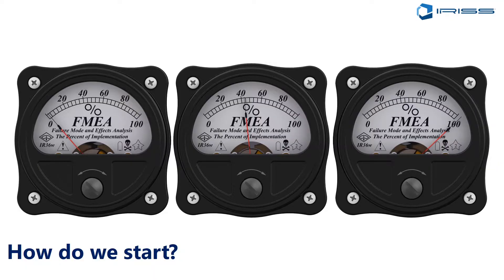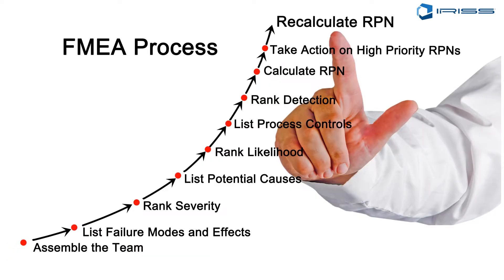So much has been written on the why and the what of electrical maintenance programs, but how can you start at your facility? We recommend performing a criticality analysis using a failure modes and effects tool set in order to determine where you should be spending the bulk of your energy to maximize reliability of your electrical infrastructure. The FMEA process is well documented and leads to calculating a risk priority number of your critical assets, then taking preventative steps to mitigate the risk on the highest priorities, and then recalculating the RPN. The process is relatively simple but is tailored to every individual facility.